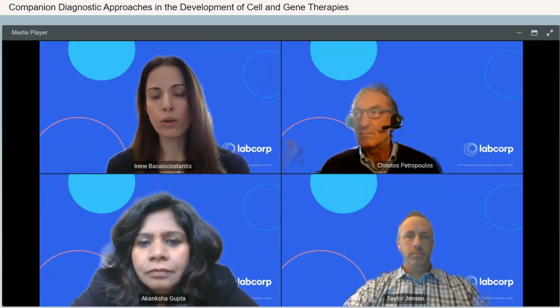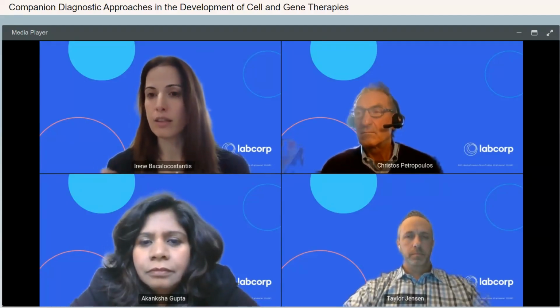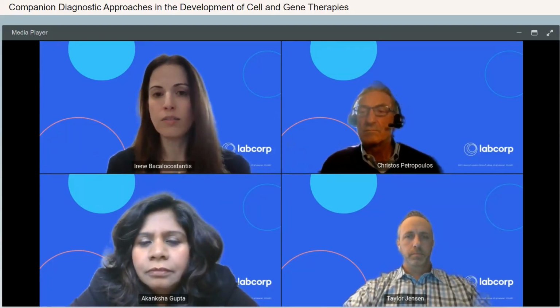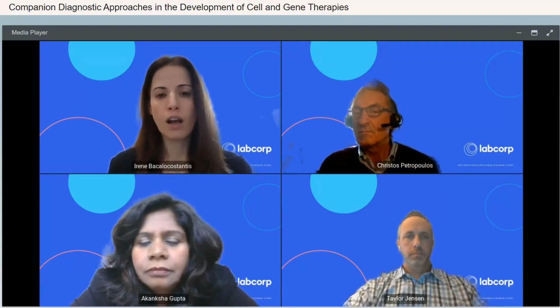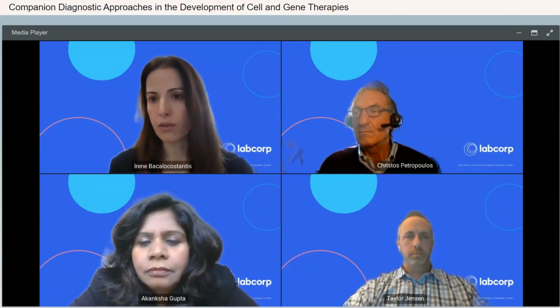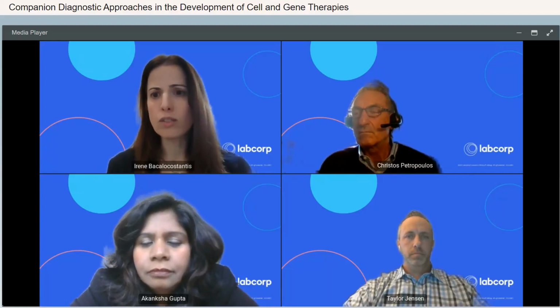Then there is a coordination process with EMA. It takes them about 3 months to send the material and have EMA prepare in order to receive the documentation. Then another 120 days in which EMA reviews and asks questions. That doesn't include the stop clock. That is their time. And then finally, upon positive opinion, we can expect the IVDR CE marking. So it's about a 2-year process.